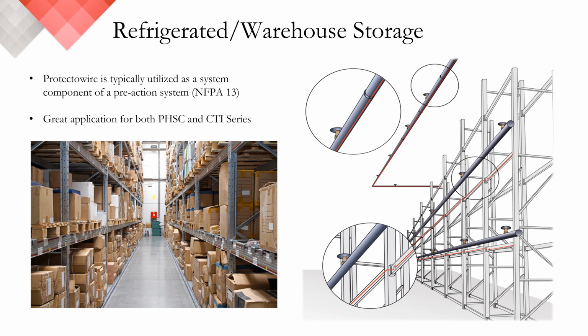One of the most popular applications for linear heat are warehouse storage and industrial freezers. In these facilities, linear heat is typically a component of the pre-action system. In freezers, it's the primary releasing mechanism for filling a dry pipe system. When installing for in-rack detection, the detector should be positioned in the flue space at the same level or alternating levels with the sprinkler pipe. Typically, it would be recommended that the detector be fixed directly to the sprinkler if possible and permitted in your jurisdiction. It's still acting as an integral part of the releasing system.